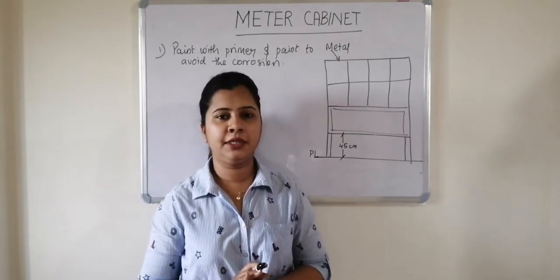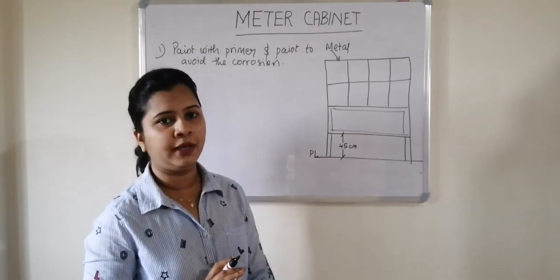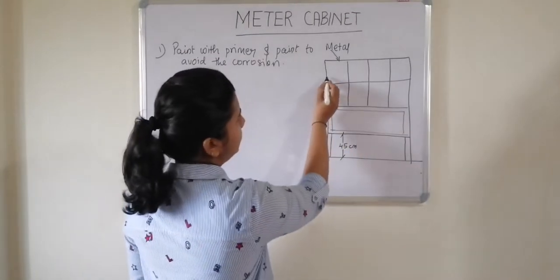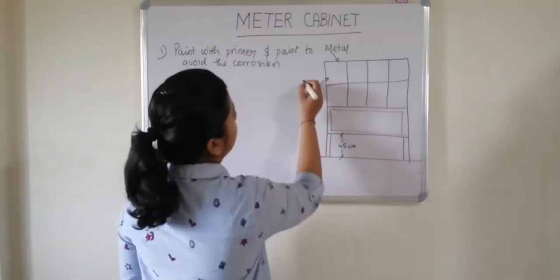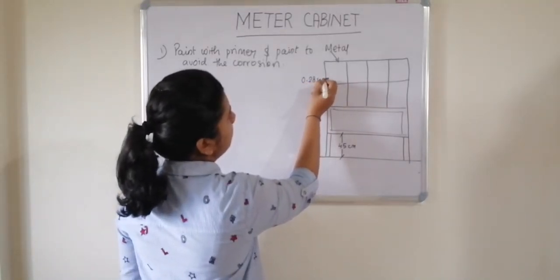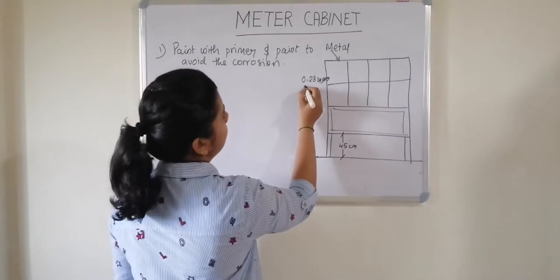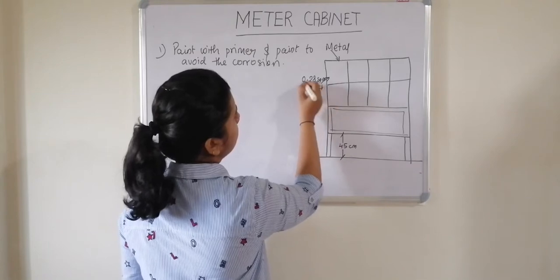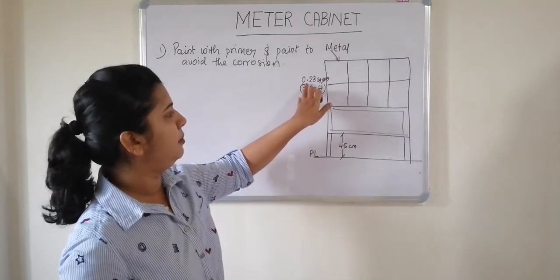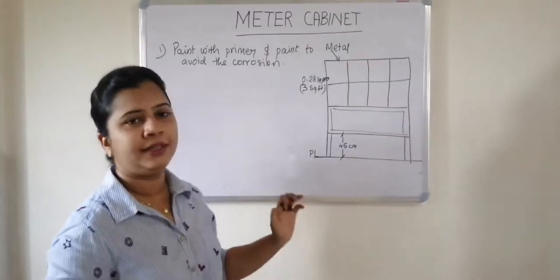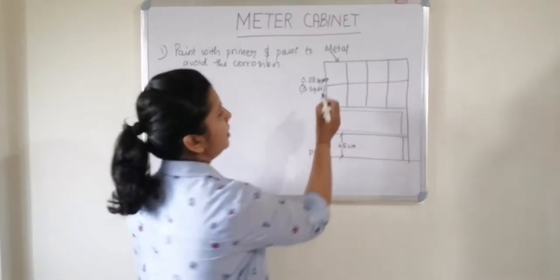Now each flat will contain one meter box, so depending on that you should calculate the size of the meter panel. Now let me tell you that one single meter box contains or consumes the size 0.28 square meter. The area consumed by a single meter box is 0.28 square meter, that is 3 square feet. A single meter box will consume minimum area of 0.28 square meter, that is 3 square feet. According to this, you will have to calculate the area of the total meter panel.